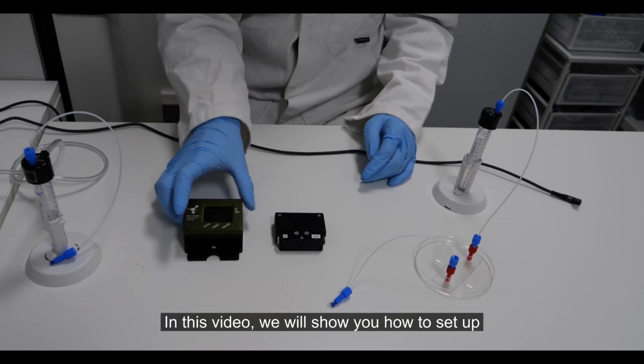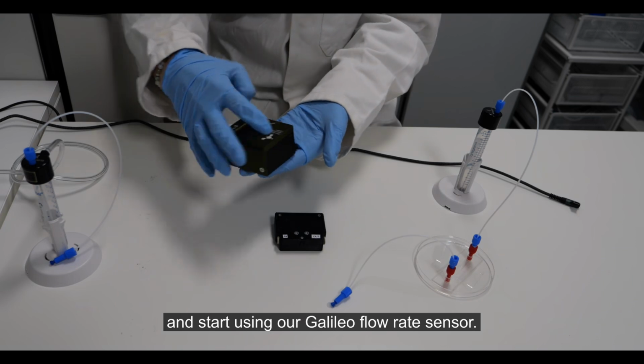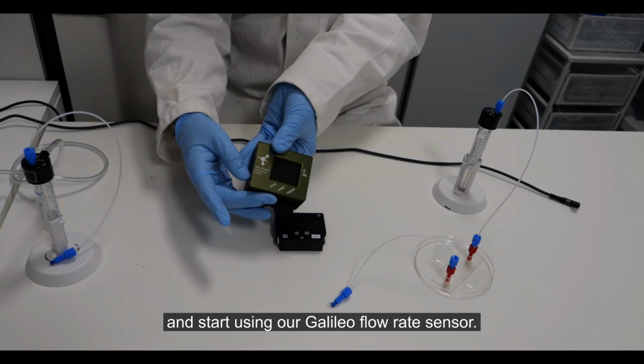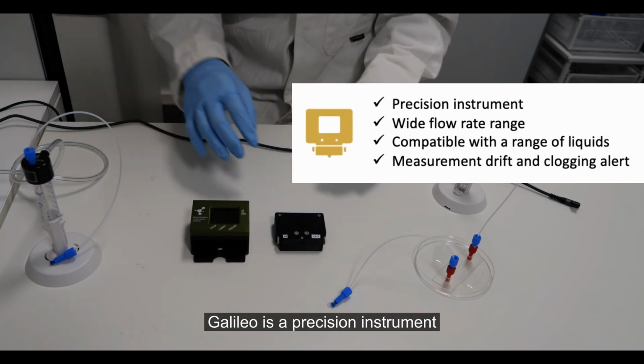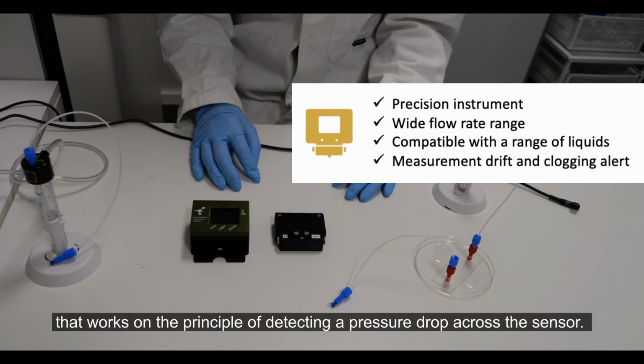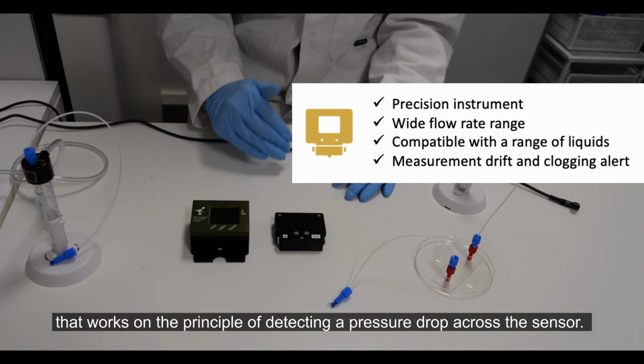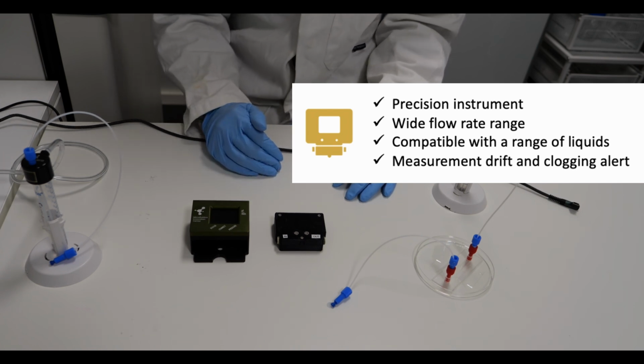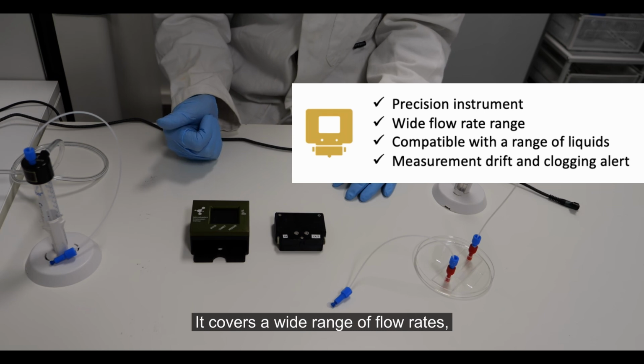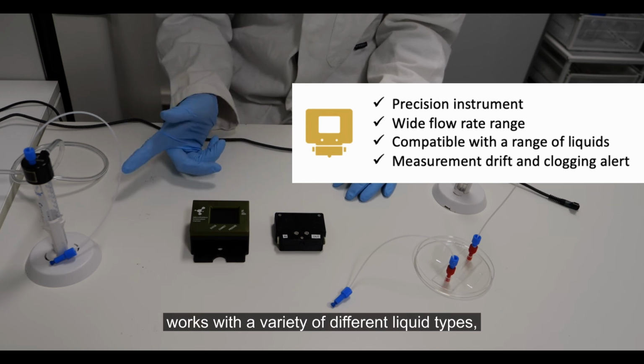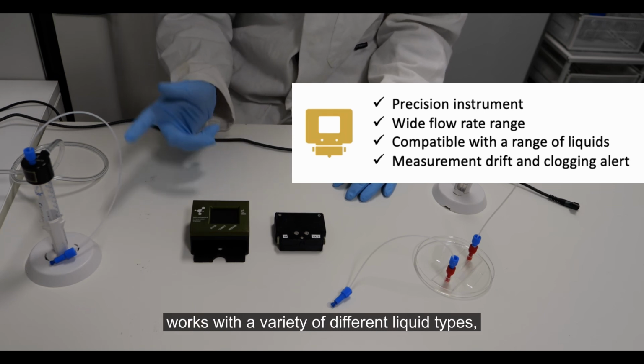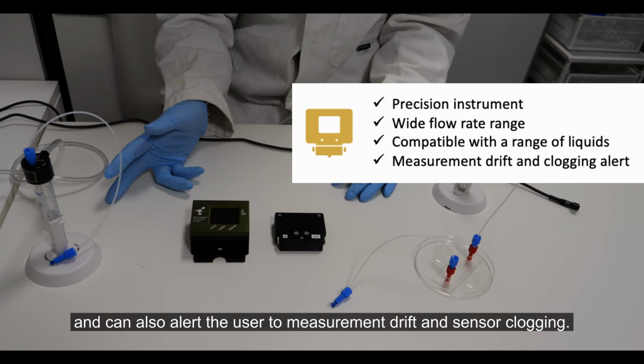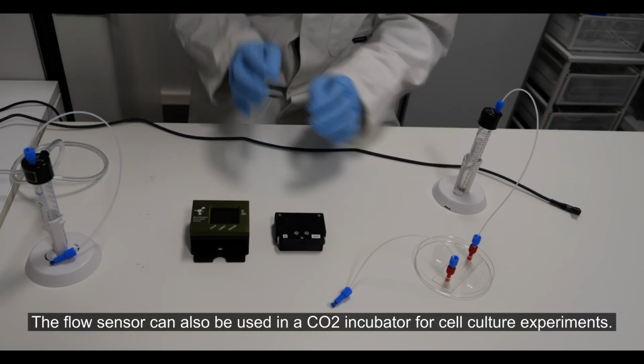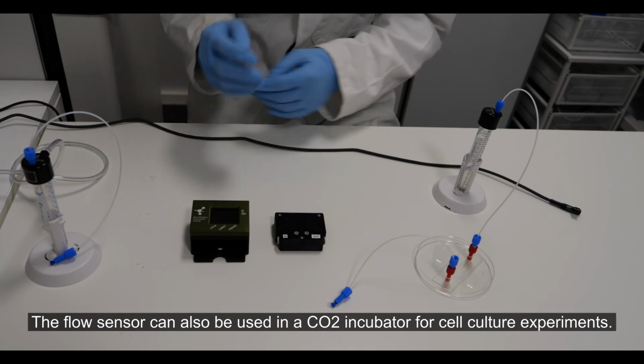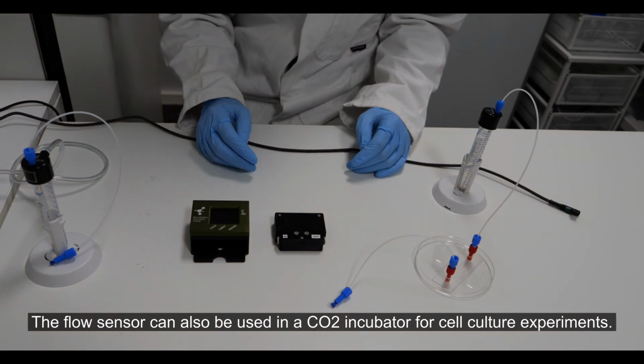In this video, we will show you how to set up and start using our Galileo flow rate sensor. Galileo is a precision instrument that works on the principle of detecting a pressure drop across the sensor. It covers a wide range of flow rates. It works with a variety of different liquid types and can alert the user to measurement drift and sensor clogging. The flow sensor can also be used in a CO2 incubator for cell culture experiments.